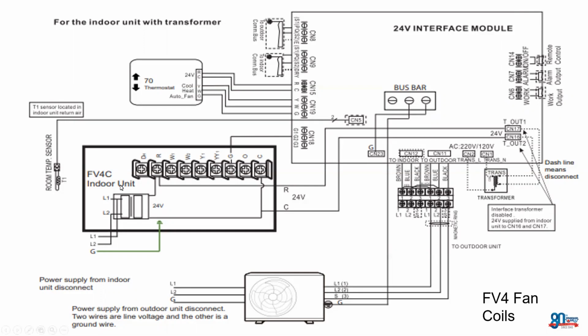Okay. Now, if we look at our FV4C printed circuit board, you'll see all that we have hooked up is R, G, and C. And that'll throw a lot of guys for a loop because you're used to seeing all your thermostat connections here. But you have to remember, we have a hybrid combination. We need to reference where our thermostat is up here and see that it hooks up to the 24-volt interface. So there are the typical thermostat connections. We're only using a G terminal to broadcast a control signal to this printed circuit board to let the system know that there is a call for a fan, and this interface broadcasts that same signal on the signal wire that feeds to our ductless outdoor unit to energize or de-energize the reversing valve, depending on what mode we're calling for.